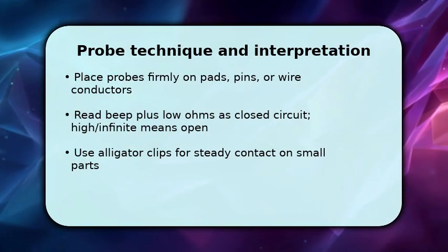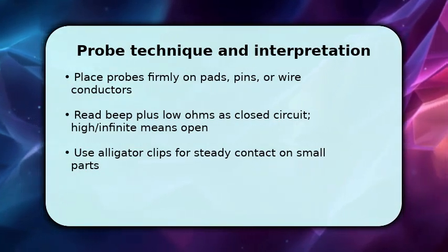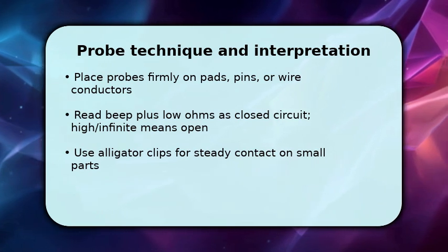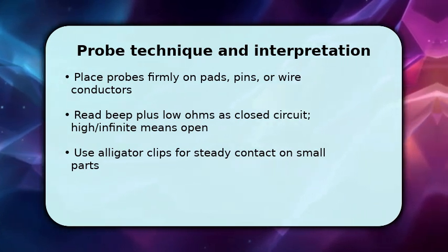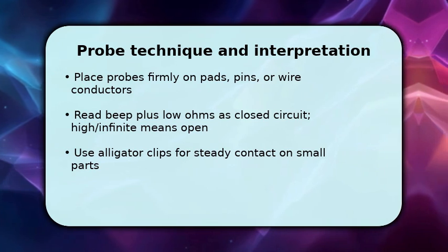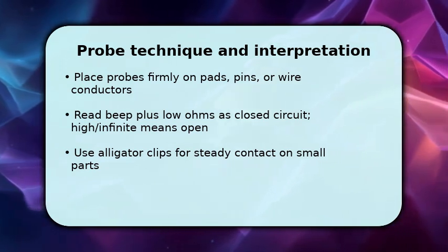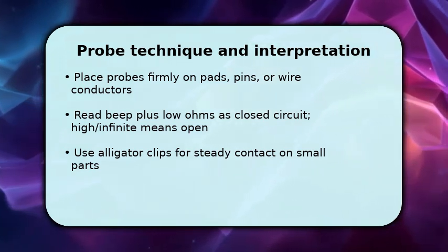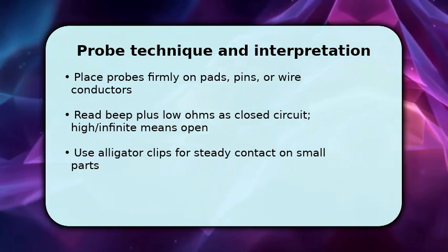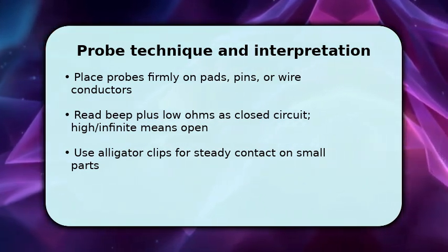With the meter confirmed, you proceed to precise probing. Place the probes solidly on the two points you want to test, holding steady to avoid intermittent contact. If the meter beeps and shows low ohms, interpret that as a closed path. If it shows high or infinity, the path is open or has very high resistance.